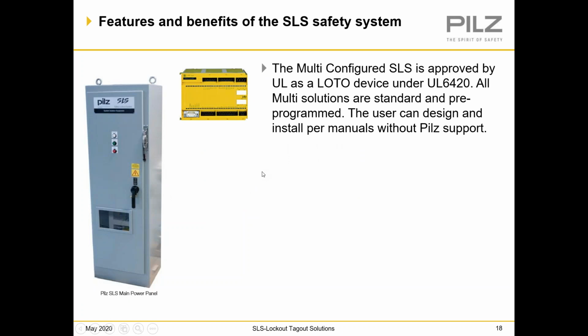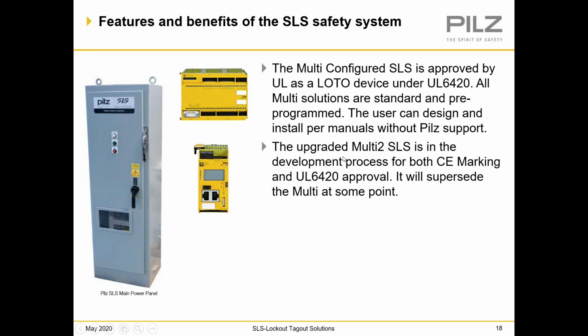There are 3 configurations in the SLS package using configurable safety relays or safety PLCs. The first one, we've had this particular design using the multi for over 20 years now, and this SLS design is a UL 6420 approved design for lockout, and all multi solutions are standard and pre-programmed. The user can design and install per manuals without Pilz support.